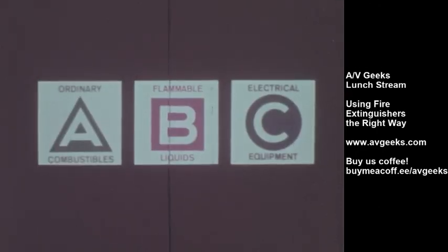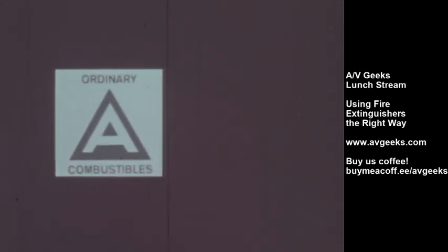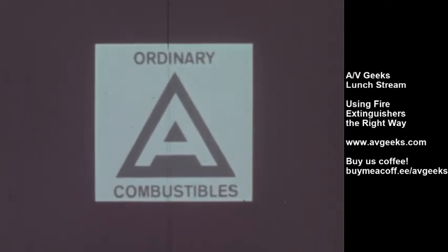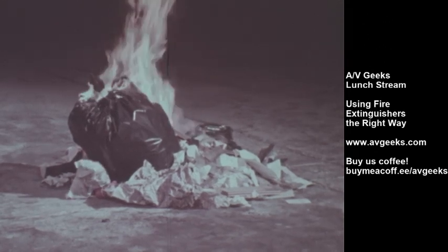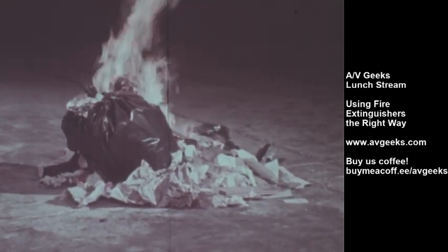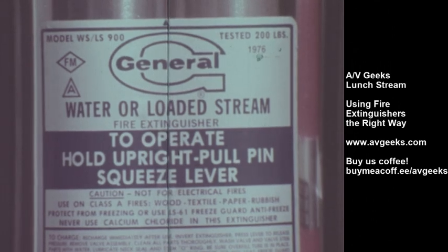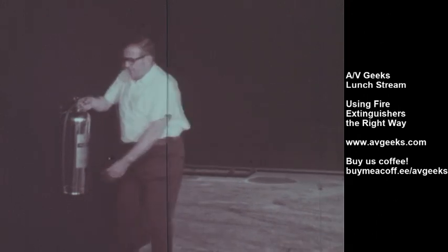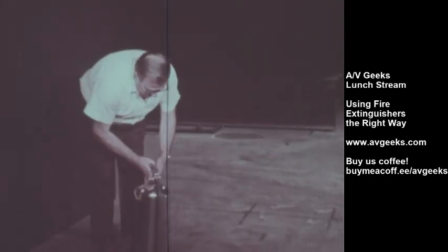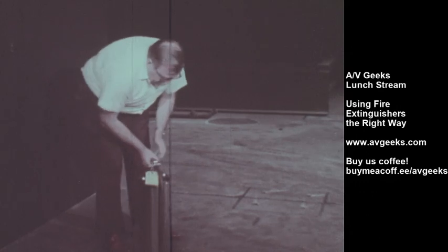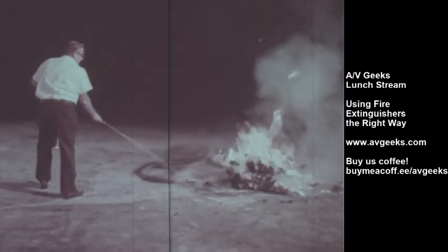For ease of selection, fire extinguishers are identified according to the ABC classification of fire hazards. Class A fires involve ordinary combustibles. The most common extinguisher intended for use exclusively on Class A fires is the pressurized water extinguisher. Using this type of extinguisher is quite simple. Hold the extinguisher upright, pull out the safety pin, and squeeze the lever. Aim the hose at the base of the fire.